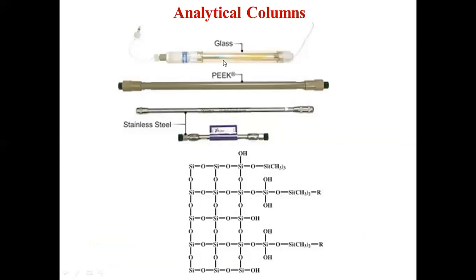These are the images of the glass column and stainless steel columns, which we can use as analytical columns. Glass column, the advantage of the glass column is we can see the band separation inside. If there are colored objects available in the sample, we can see the separated bands. If the species is colorless, we cannot. Of course, we can see the movement of the liquid through the column. However, the stainless steel columns are going to be used most commonly, and the packing material may be like this, or it may be a modified one other than this.